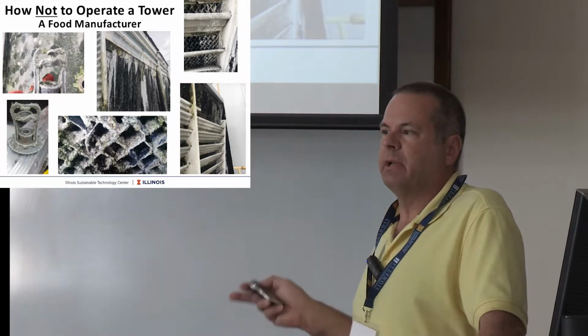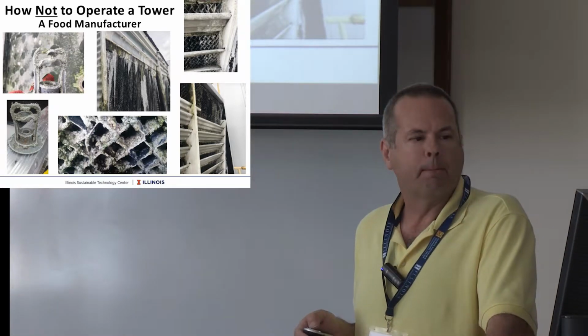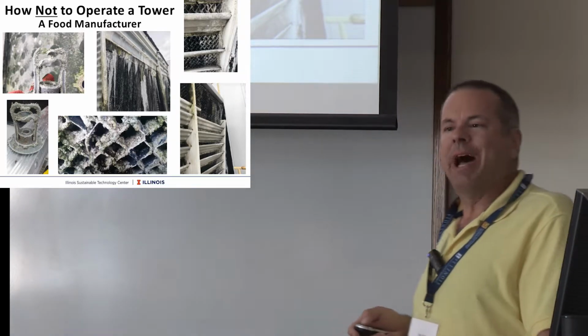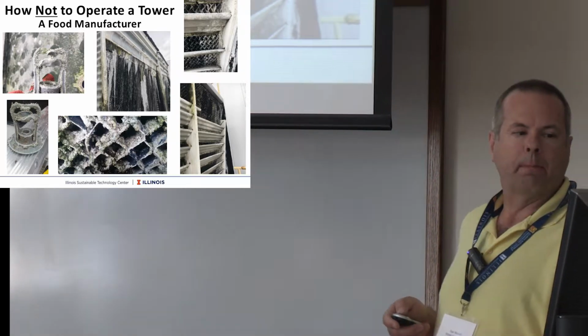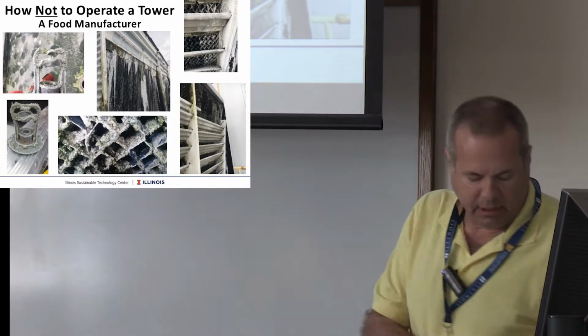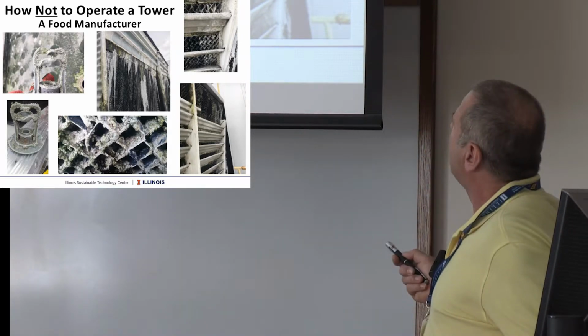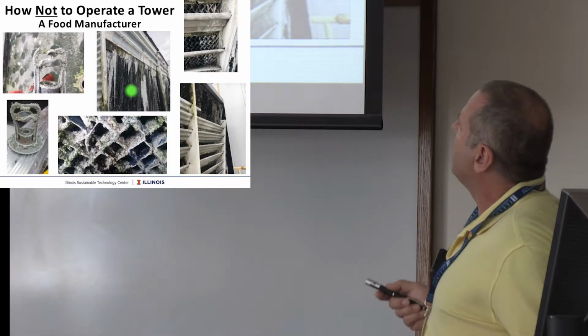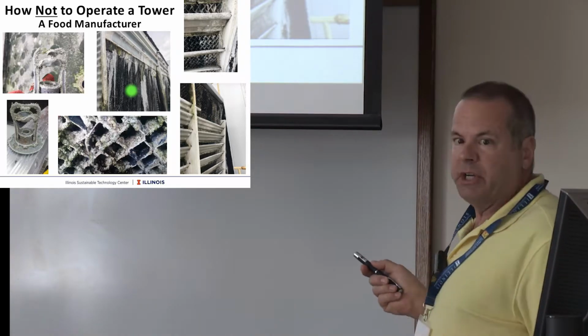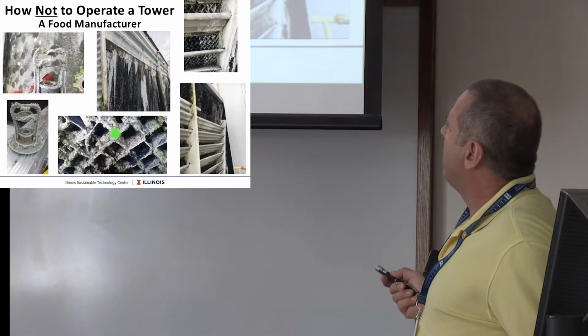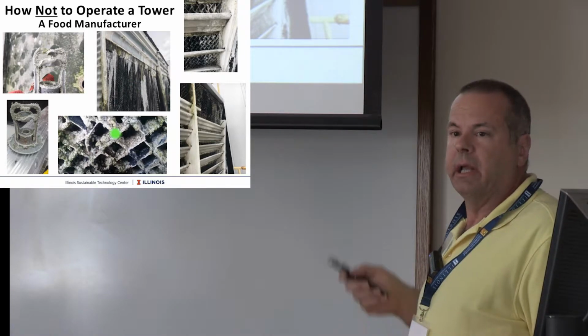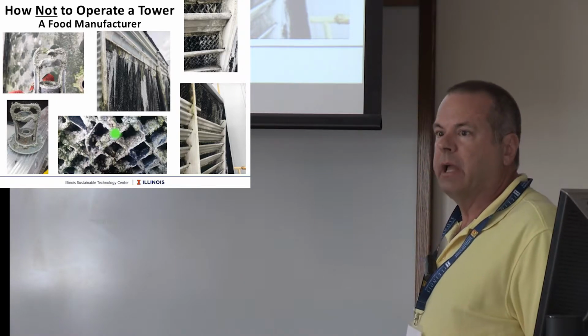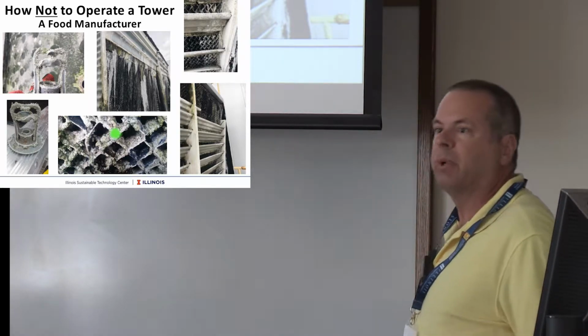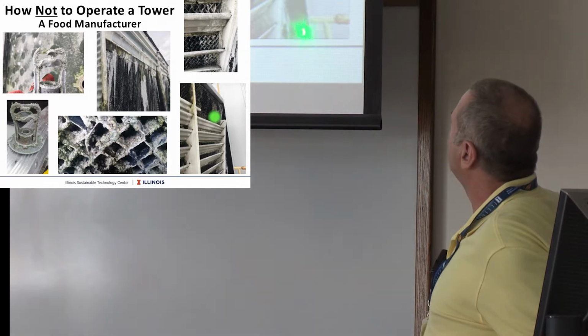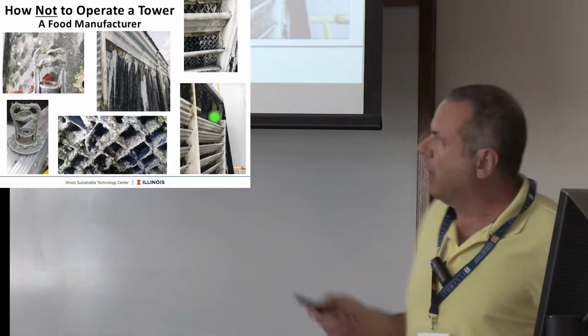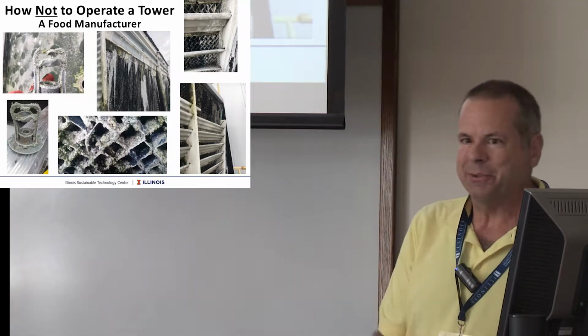Now, this is not a picture of anybody's cooling tower here in this room, but it is a food manufacturer. How not to operate your cooling tower. I'm not sure if you can see everything here, but I'm just going to point out one thing. In this picture, you've got ice buildup, you've got algae growing in there. Right here, you've got the fill that's deteriorating. It's actually falling down into the bed. It's going downstream into their chillers, plugging up lines, really causing problems there. You have broken louvers and you've got a lot of corrosion. So they're having some chemistry issues there, obviously.